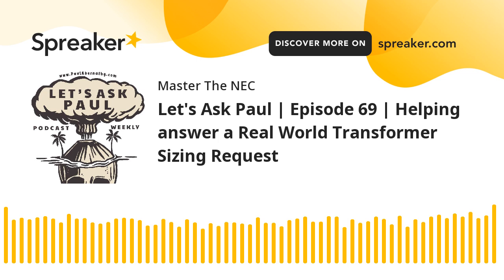So a 30 kVA is going to handle your 78 amps, okay. A 45 kVA would handle more amps. And if you do the same type of math, 45,000 divided by 360 is going to be 125 amps, which many people that design these systems say gives you a little bit of an extra cushion on this transformer.